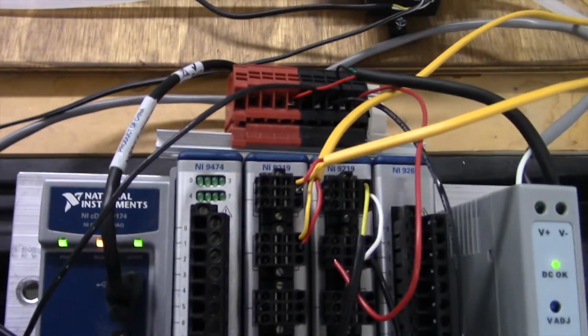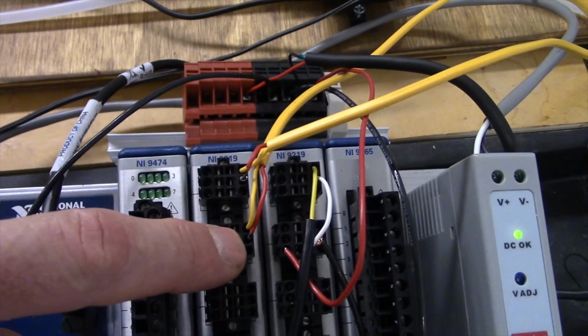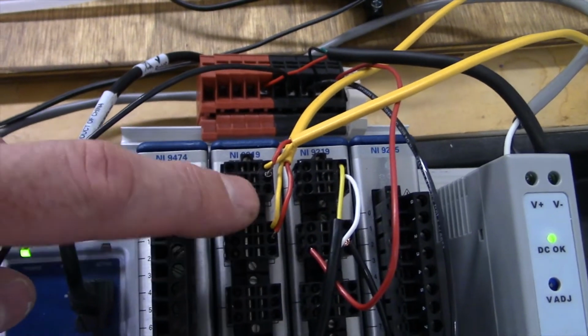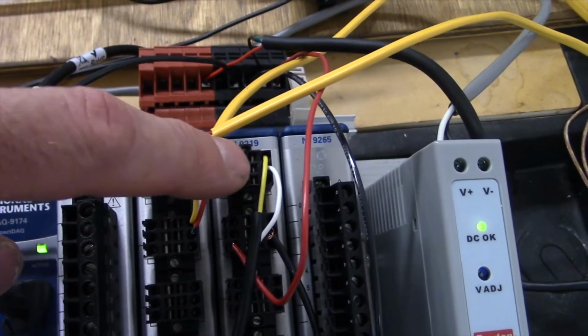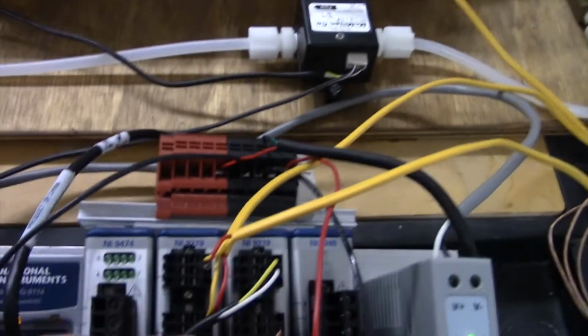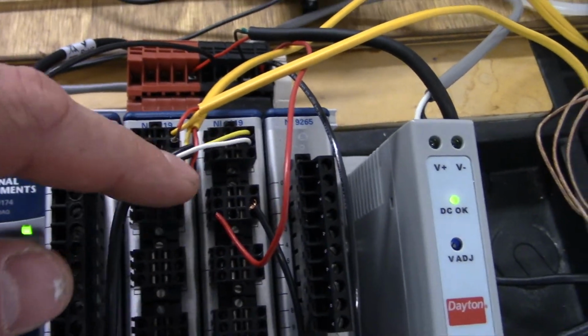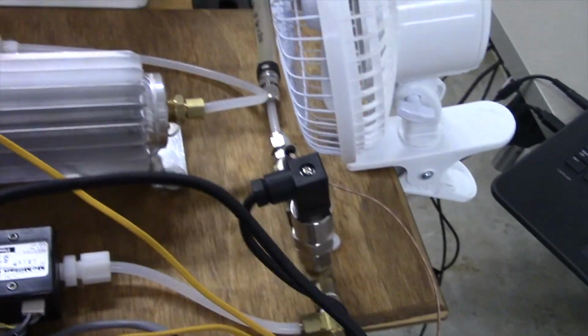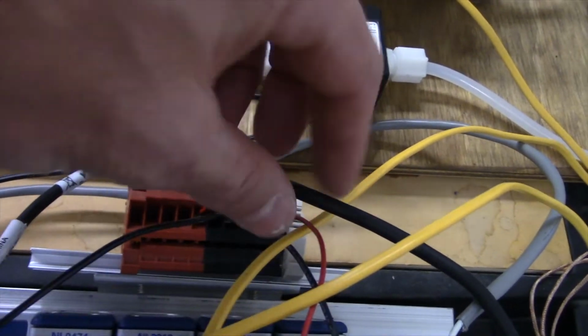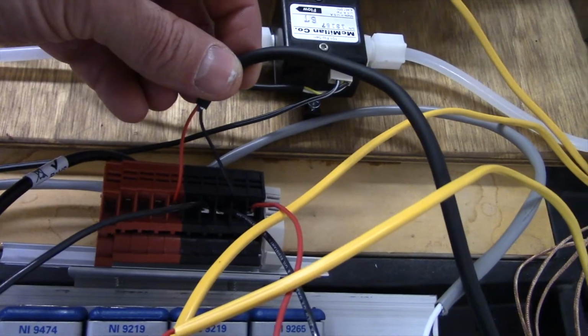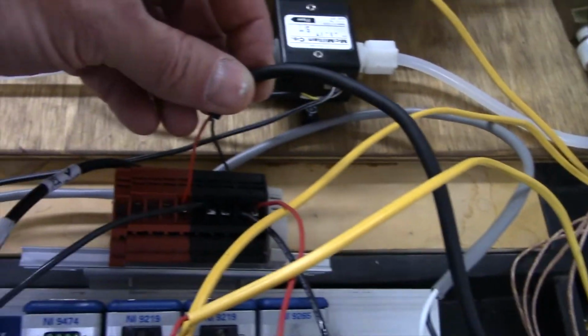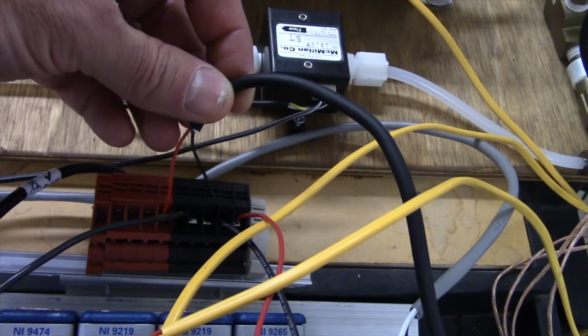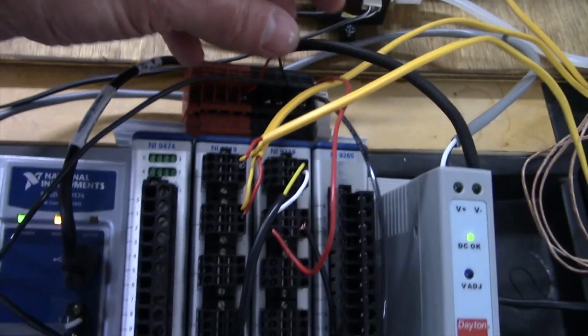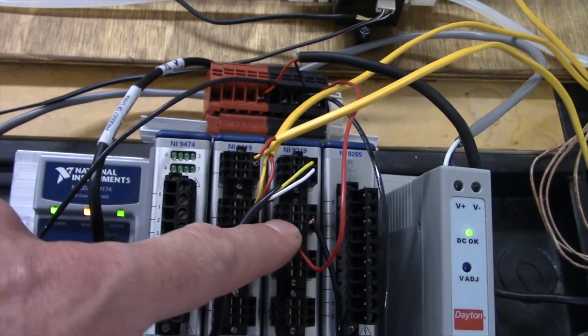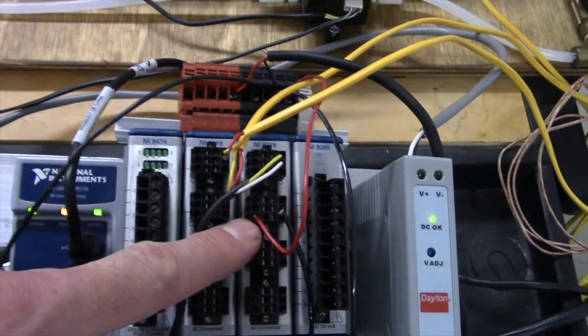So that's measuring a voltage, similar to the thermocouples measuring temperature here. Here it's measuring flow by voltage. Thermocouples also measure voltage, and they're wired similarly to the flow. This is where the pressure is being measured, and it's measuring the current. In this particular setup, the pressure sensor has two leads, simply a positive and negative, and so it's being powered. At the same time, it's using those same two wires to allow a signal through. So it powers it, and then in a loop kind of manner, you measure the current. You wire it in series with the data collection, and this data collection port is measuring the current.